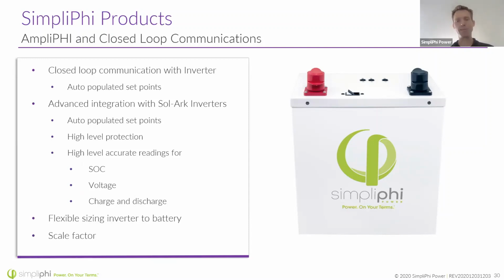So if you hook up 4 of these batteries in a bank, the battery's BMS system will automatically detect other batteries in the bank and know how many are there. It will know how to set the parameters inside the inverters and charge controllers. This advanced integration works very well with solar inverters, like the Briggs and Stratton inverter, and you get automatically populated set points and high level protection as well.